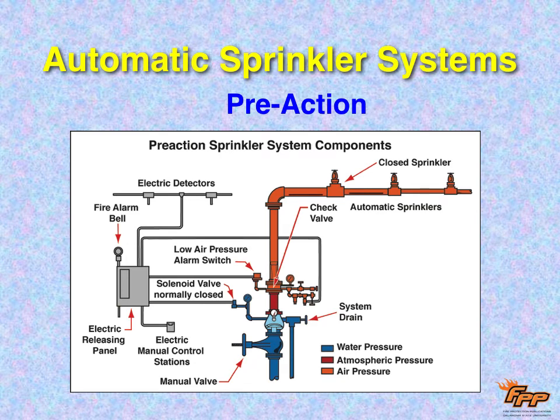So pre-action is a combination of a deluge system and a dry pipe system. In a pre-action, the sprinkler heads are closed, though, unlike deluge. They're like the dry pipe, but there's no air pressure in there. There's just regular air. And there's a check valve and a valve that holds the water back like the deluge. So the valve is similar. But what we're going to do here is, the problem with dry pipe is it's a slow process. By the time all the air pressure comes out and then the water comes in, there's a delay.